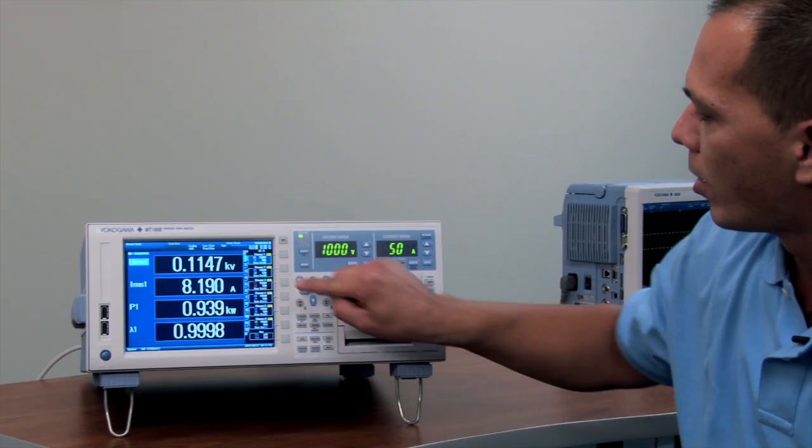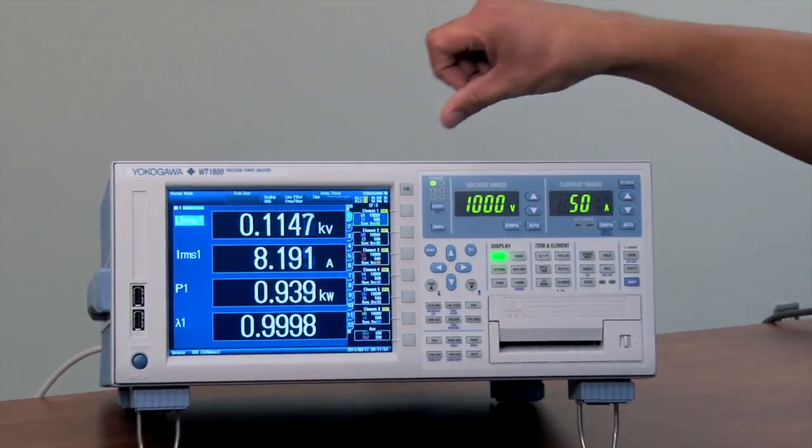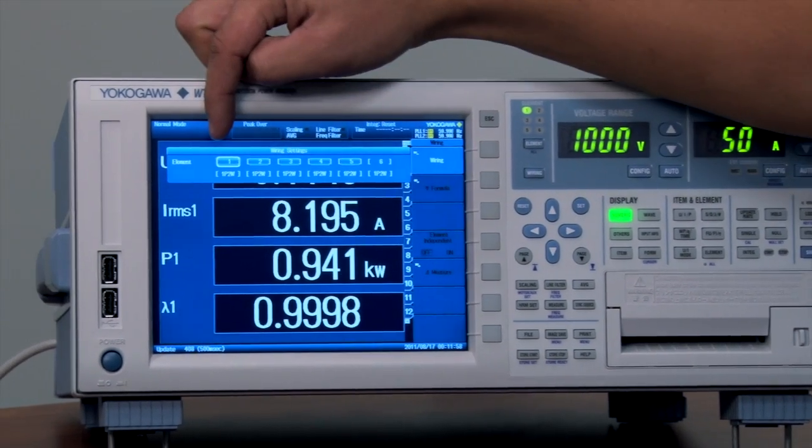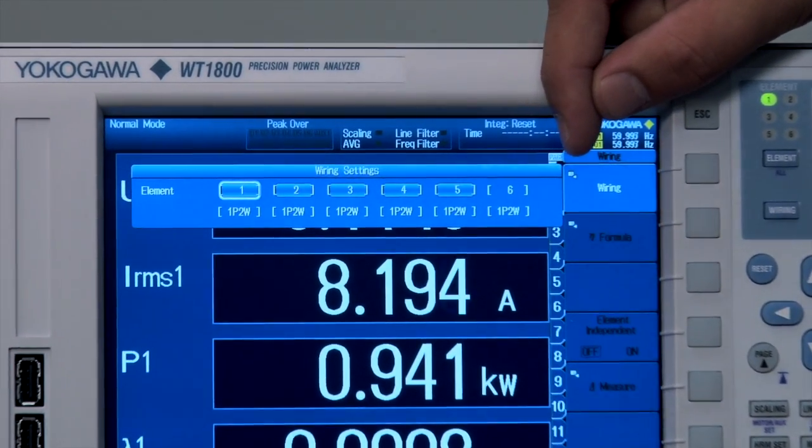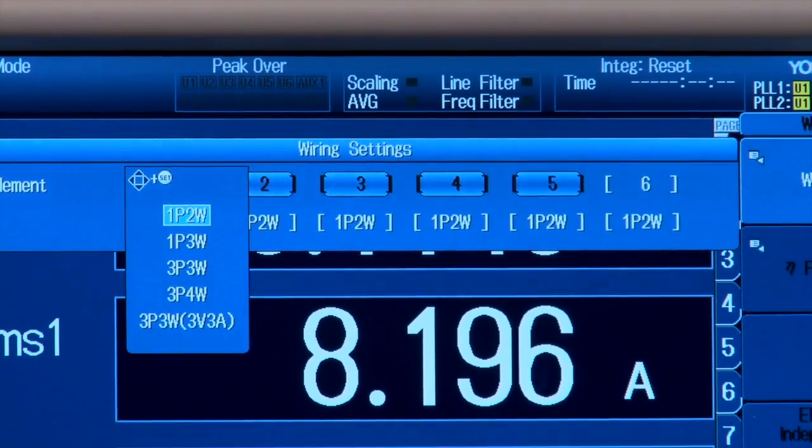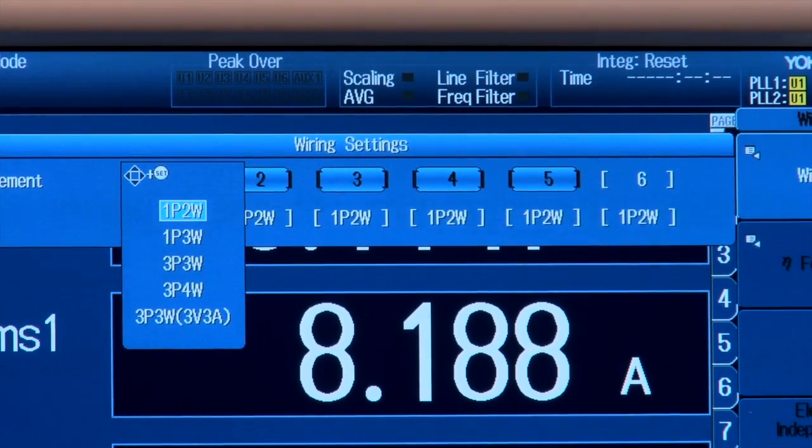The WT1800 is very easy to set up. Once you wire up the unit in the back, it's a matter of telling the instrument how you're wired. You start by keeping either of the six input elements as single phase inputs, or you can easily switch and select three phase so you can have a combination of a three phase input and output of an inverter, for example, to compute efficiency.